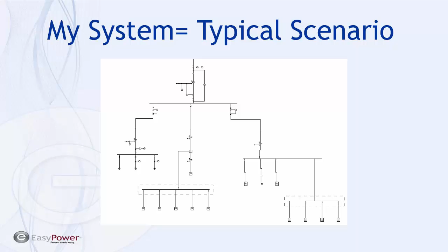Let me go to this reference material available on the EasyPower website. The first is Data Collection for Arc Flash Hazard Study. These are literally the notes we provide when people take a data collection class from us, and they're available for download, or you can contact me or sales@easypower.com to request this document free of cost. Secondarily, and even more strongly, I suggest you download the Arc Flash Reference Guide, entitled Practical Solution Guide to Arc Flash Hazards, since it's too large to email. It's been updated to the NFPA 70E 2015 standards, and it's quite literally a step-by-step guide on how to use EasyPower tools in conducting an arc flash study.